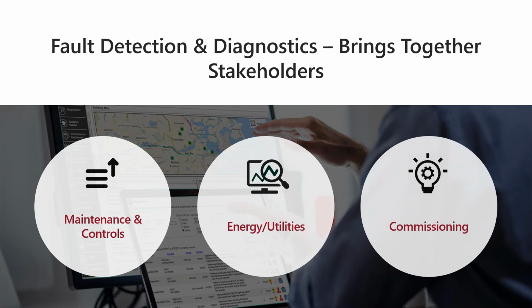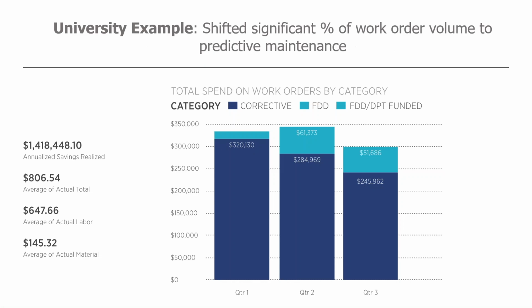We see energy engineers and utilities groups using the tool to look at a top-down perspective, so to be able to benchmark buildings, to look at the energy consumption, normalized, as well as key performance indicators. So I'll come back to that a little bit. Energy key performance indicators like heating efficiency, ventilation efficiency, cooling efficiency. And then commissioning teams, whether that's in-house teams or outsourced vendors. There's a lot to be said there, so we'll come back on that. But having fault detection diagnostics and technology do some of the heavy lifting of the commissioning process, and again, being able to transition from commissioning as a one-time event to a continuous process is really what that tends to look like.